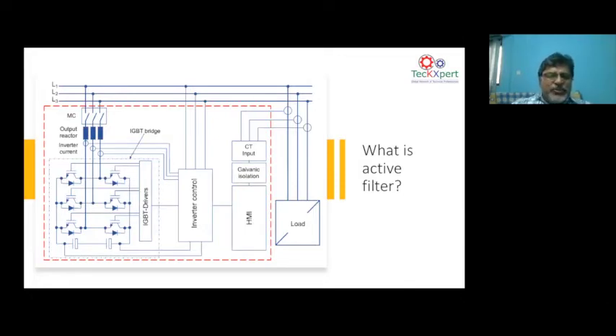And again, as you see here, this IGBT concept is called a two-level topology. That is, it has 6 IGBTs. The latest active filters have 12 IGBTs. We call it a 3-level topology. A 3-level topology has a lot of advantages over a 2-level active filter, in terms of noise, in terms of life, in terms of losses, in terms of size, and in terms of the overall cost of ownership. You can bring down the total cost of an active filter by going from 2-level topology to 3-level topology.